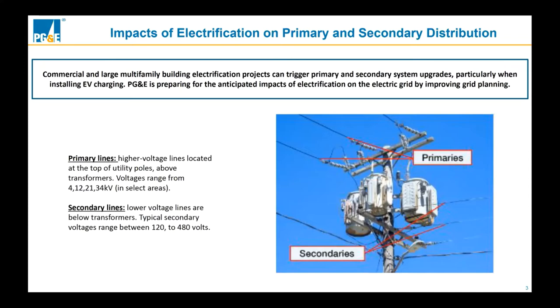So that's primary and secondary. To bring this back to commercial and large multifamily buildings, unlike single family buildings discussed in the last webinar, where a lot of the electrification drove upgrades primarily on the secondary system, with commercial and large multifamily buildings, depending on size, that can drive upgrades on not just the secondary, but the primary distribution system as well. And if it's really large, like some of the examples Barry was going through, you could see needed upgrades maybe as upstream as the substation.